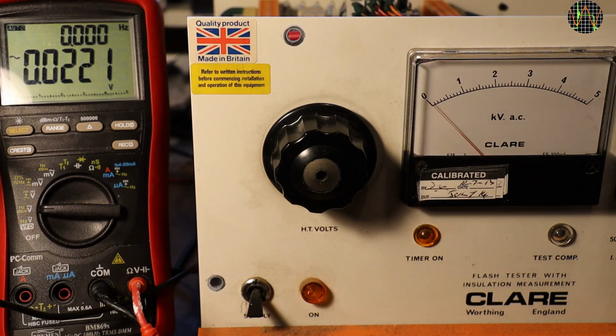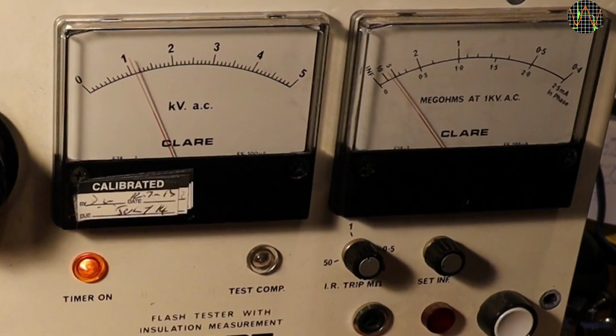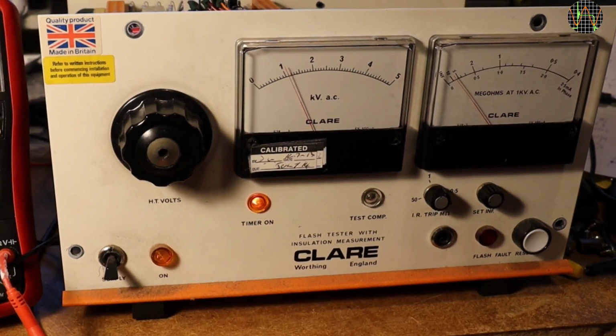I connected my BM869S in parallel with the AVO using a divide by 1000 probe. The 1.0243 volts it shows is therefore 1024.3 volts, which agrees with the meter on the CLARE. I run a test at 1 kilovolt and let me freeze the video for a moment. The AVO 8 has a rather low input resistance of about 2.5 megohm in the 2500 volt AC range. This means, according to what's written on the meter, megohms at 1 kilovolt, I would expect the needle very close to the left of the two, but instead it is showing over 5 megohm.